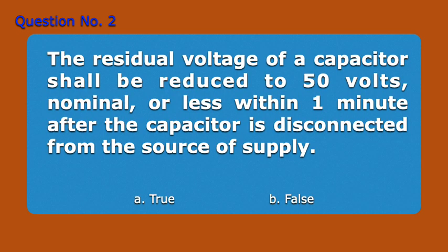Question number 2. The residual voltage of a capacitor shall be reduced to 50 volts nominal or less within 1 minute after the capacitor is disconnected from the source of supply. A. True. B. False. Answer: A.